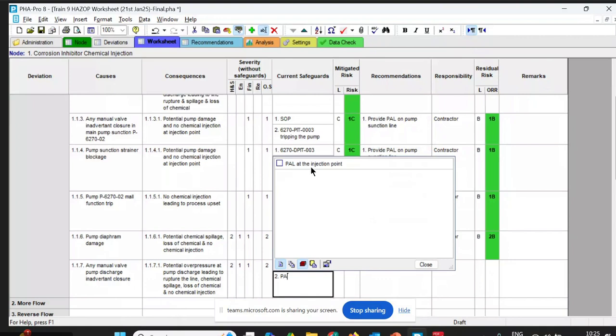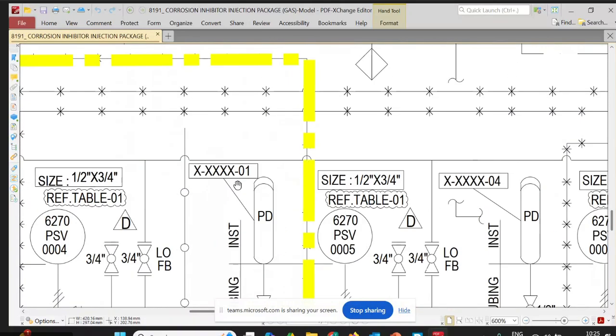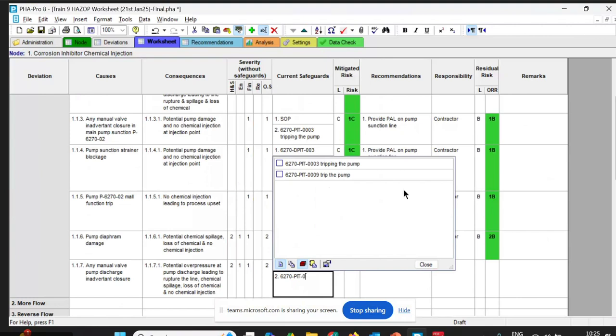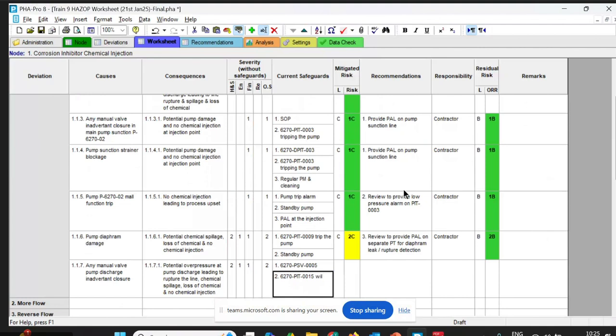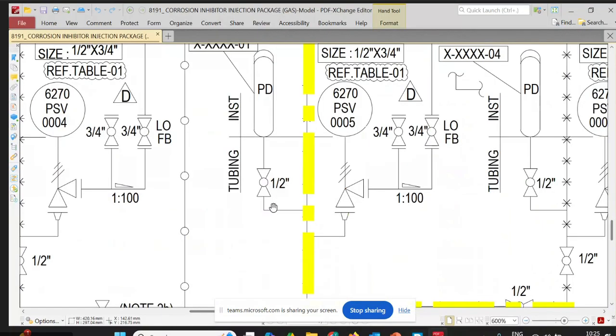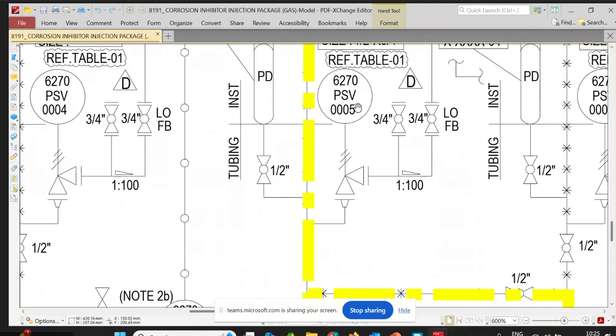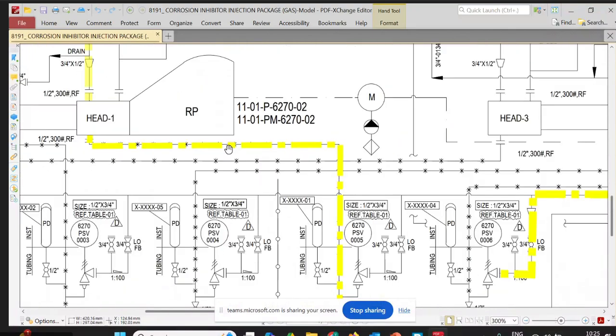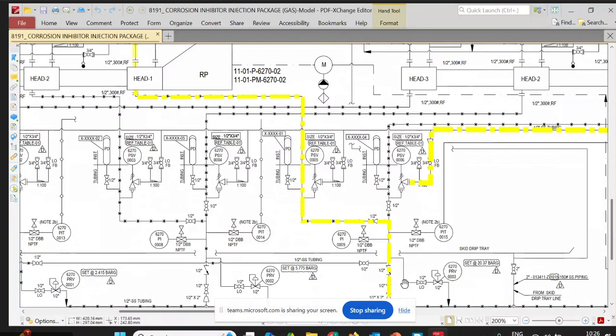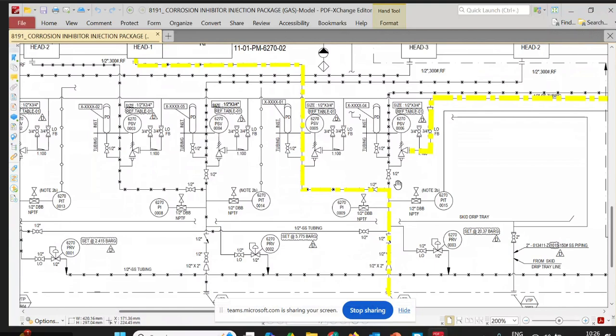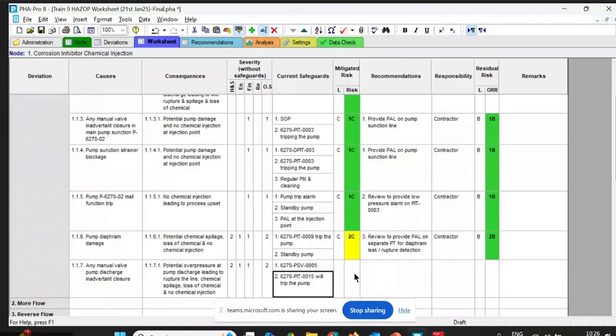6270 PIT. Rajesh, what is the PAHH? 0015. It will trip the pump, right? Yeah, it will trip the pump. Yes. So guys, for the overpressure case, we have very good safeguards. We have got a PSV and we have got PAHH. It will trip the running pump, so that in case of any inadvertent closure of the manual valve, we can protect the piping system so that there is no rupture, no chemical spillage. So we are happy. In this case we are okay because we have a lot of safeguards.